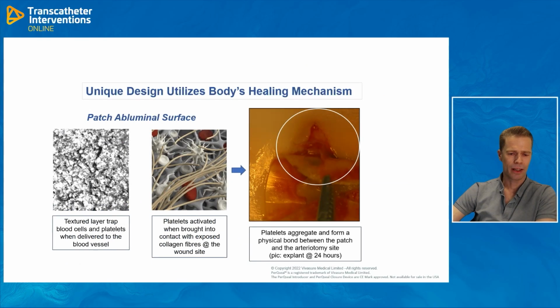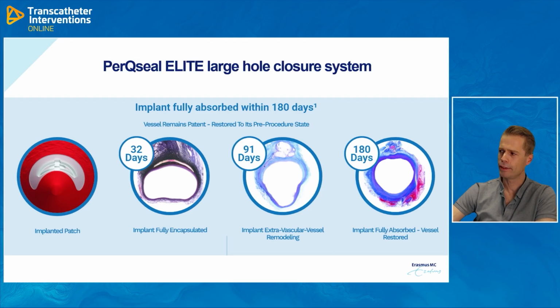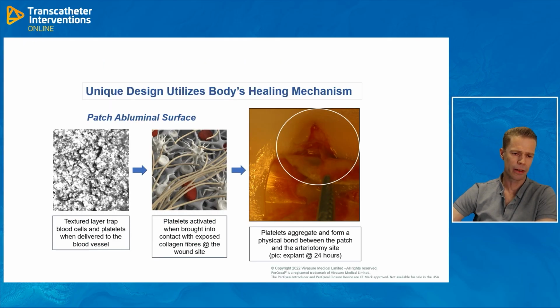So what happens with the patch when it is implanted into the blood vessel? If you take the patch and look at the left image here under a microscope, you will see a textured layer. This is designed to really trap the blood cells and the platelets when the patch is delivered to the blood vessel. The platelets get activated when brought into contact with the collagen fibers of the wound itself, and therefore platelet aggregation results in more physical binding between the patch and the arteriotomy site. So that's really the detailed explanation of the device.